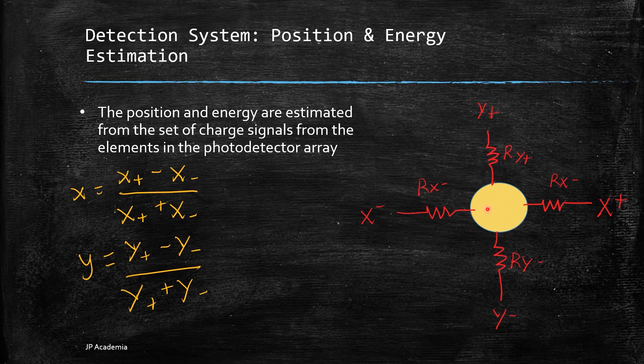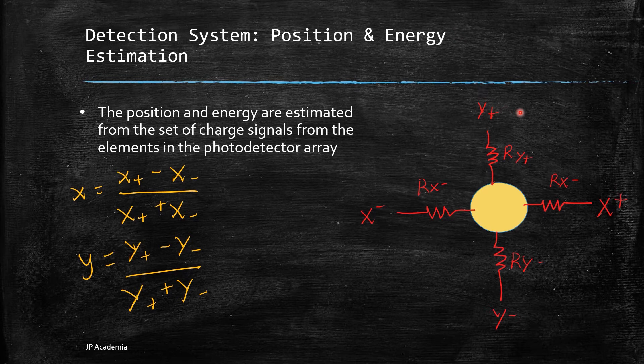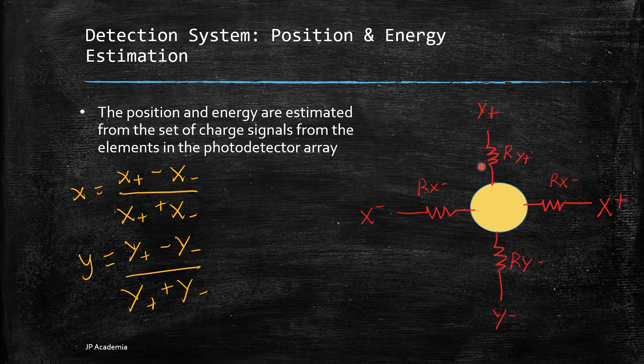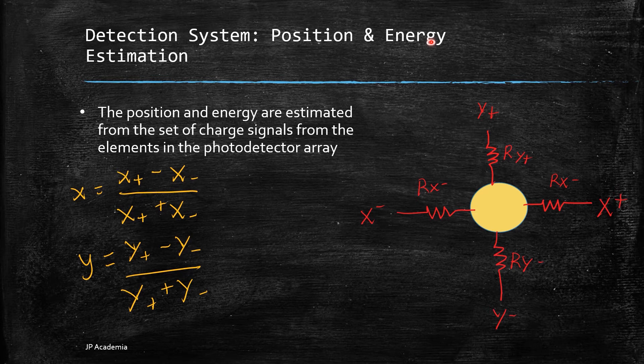Then we have four outputs. The output from each PMT or pre-amplifier is divided by a resistive network with four outputs. We have X plus with a resistor, X minus another resistor, Y plus with another resistor in between, and Y minus with another resistor. Thus, we can determine the position using the signals on these four output lines.